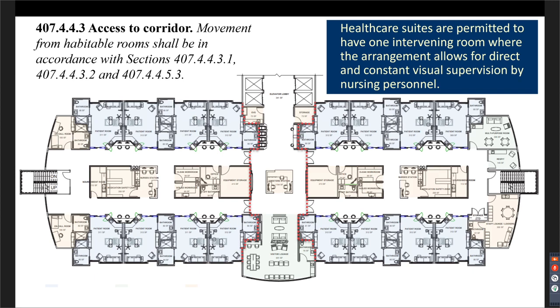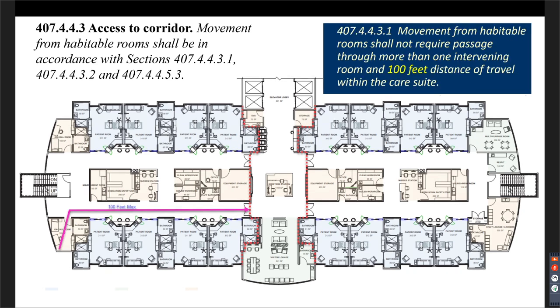So direct and constant visual supervision is defined actually by the state fire marshal in one of their interpretations. And one of the questions that comes up pretty regularly is, can I use video cameras to achieve my direct and constant visual supervision? And specifically that interpretation says, no, you cannot. So we are allowed to travel from my space within my suite through one intervening room. That non-rated corridor outside of the room is considered that one intervening room. And my travel distance limitation from the room to the fire barrier suite boundary is 100 feet maximum.